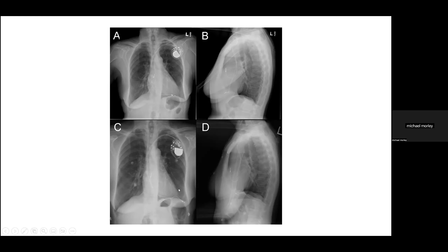So this patient attends A&E, complaining of symptoms similar to before they had their pacemaker implanted. And just for time, I'll talk you through it. So you can see pacing spikes, which are not capturing. There is no ventricular beat immediately after the pacing spikes. So we've got loss of capture, but also the pacing spikes just seem to be marching through the intrinsic rhythm. So it looks as if the pacemaker is not sensing ventricular activity. So there's a failure to capture, there's failure of pacing, there's failure of sensing.